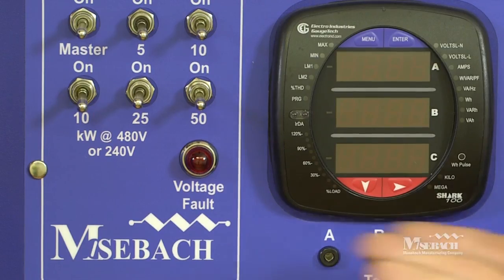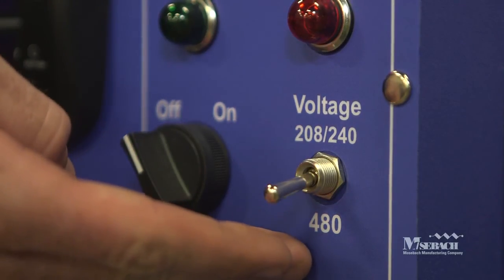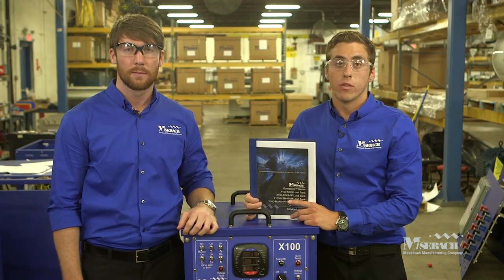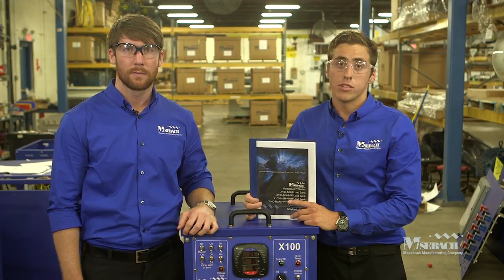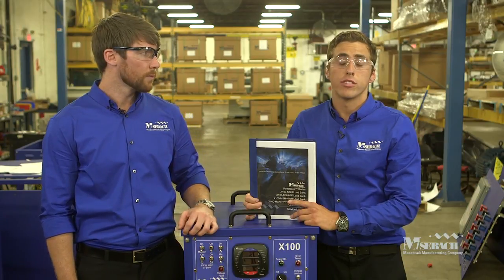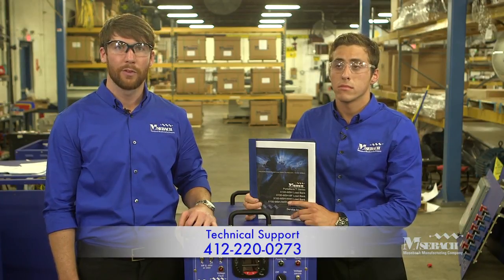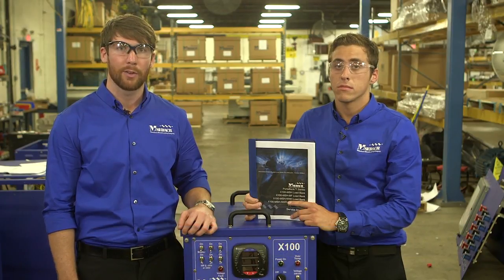Ensure that you are operating your load bank in a suitable environment. If the red over voltage indicator lamp illuminates, check two things: first, check the voltage selector switch on the front of the load bank and ensure it's set to the proper position. If it is, check your source and ensure that the voltage from the source is as expected. We hope you found the information in this video useful, but if you have any additional questions, you can consult your X100 operations and service manual, or contact Misebach Technical Support at 412-220-0273. Thank you for your time and we hope your X100 load bank serves you well.